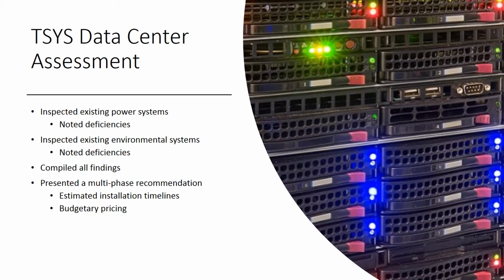While inspecting the existing power systems, K&A found the following deficiencies. Number 1. The single 1600 amp ATS is a single point of failure for the emergency power system. Number 2. Panel EDP is a single point of failure for the emergency power system. Number 3. The breaker feeding the 175 kVA UPS is not large enough to use the full capacity of the UPS. While inspecting the existing environmental systems, K&A found the following deficiencies. Number 1. The data center computer room air conditioning units do not have redundant electrical power.